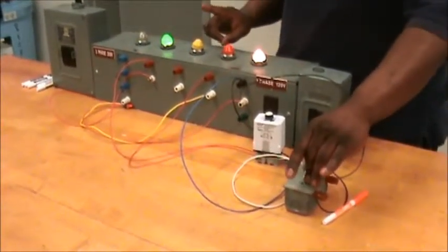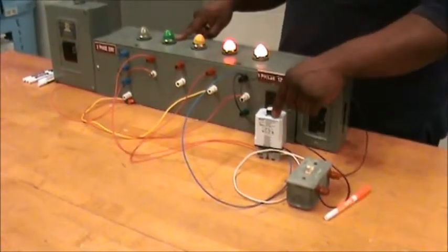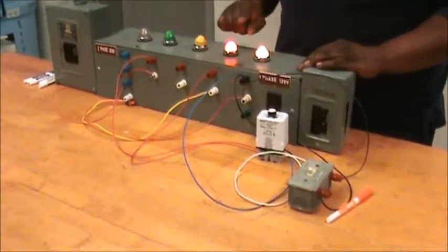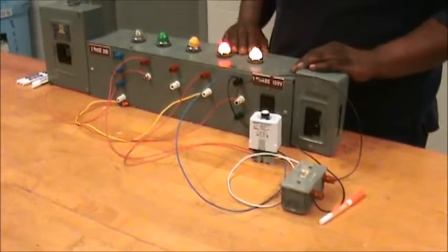When I flip the switch, there's a delay. Now that the coil is energized, after the time is done, the contacts change their state. Green light goes off, red light comes on.